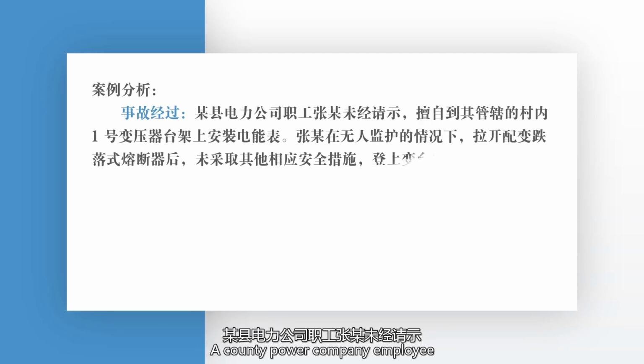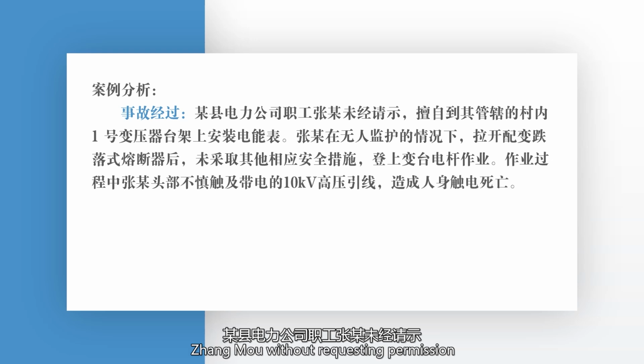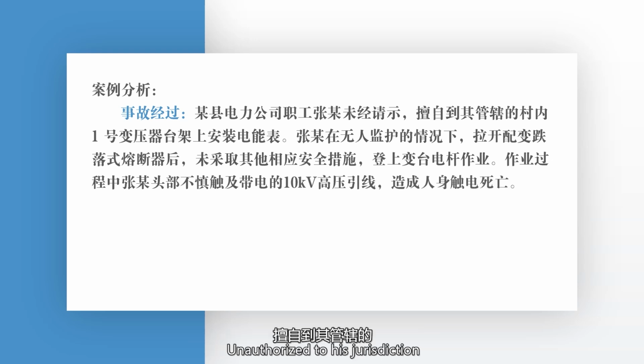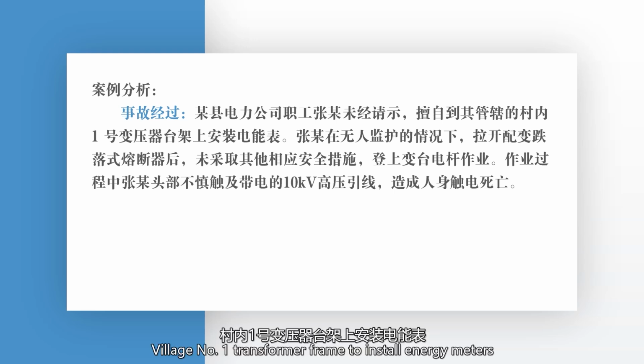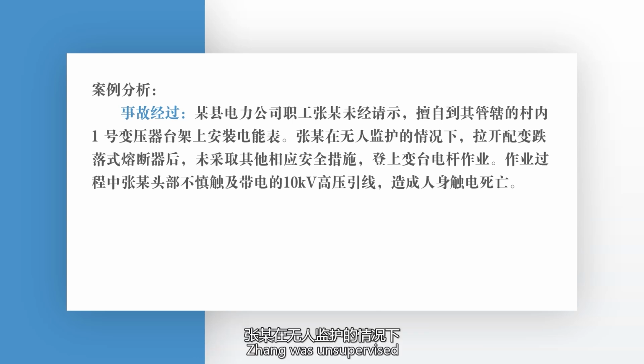A county power company employee, Zhang Mo, without requesting permission, unauthorized to his jurisdiction, village number 1 transformer frame to install energy meters. Zhang was unsupervised. After pulling the transformer drop fuse, without taking other appropriate safety measures, climbed the transformer pole to operate. During the operation, Zhang's head accidentally touched the electrified 10 kilovolt high voltage line, resulting in death by electrocution.